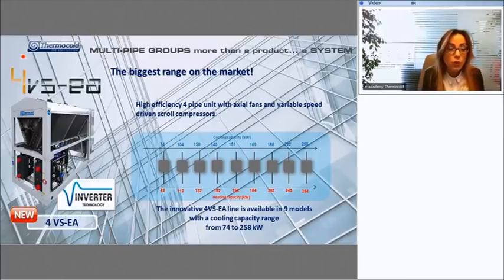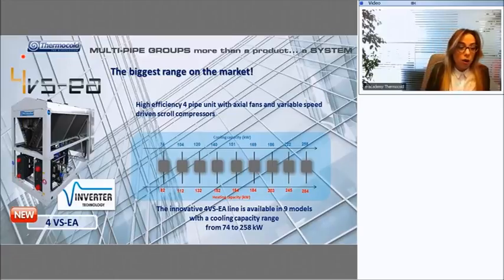What is the evolution of the 4-pipe system? You know that the Thermocold in its range has also the 6-pipe unit. So together with the 4-pipe unit, we redesigned also automatically the 6-pipe. What is the 6-pipe unit? The 6-pipe unit is a 4-pipe unit equipped with an additional desuperheater for the partial recovery.